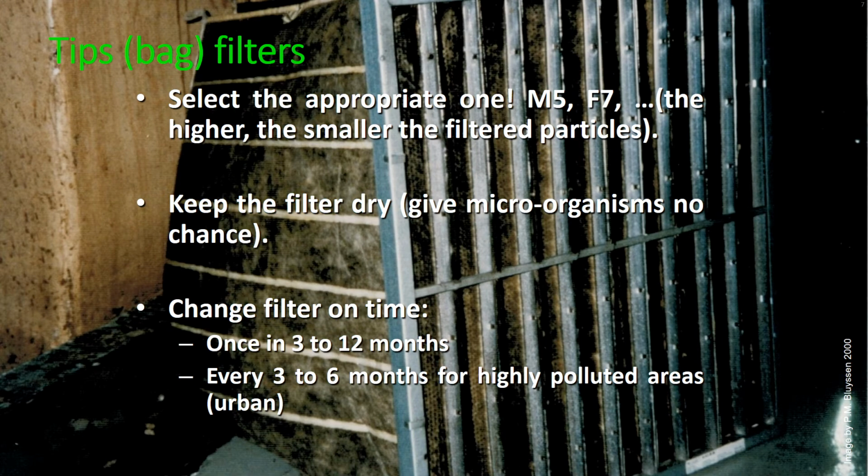Once you have selected the appropriate filter, you install this filter properly, without leaks around the frame and the ceiling seat. To prevent filters from becoming a source of pollution, it is important to give microorganisms no chance, therefore keeping the filter dry. This can be established by a proper layout of the air intake section to prevent rain and snow entering the HVAC system. By heating the supply air with a preheater or heating the filters for a certain period of time. And by preventing filter bags from lying on the bottom of the filter section when the HVAC system is not in operation.